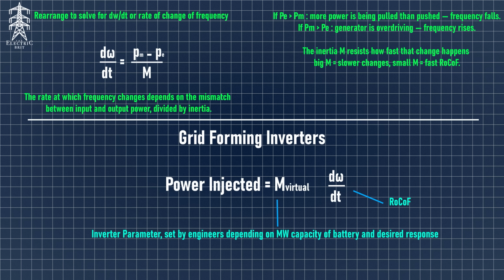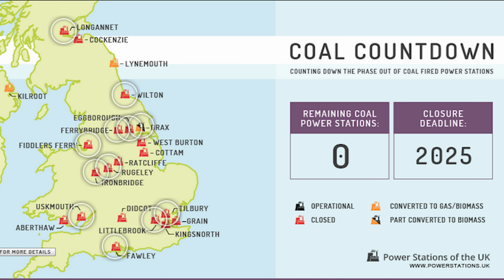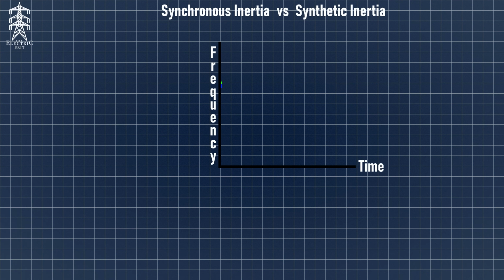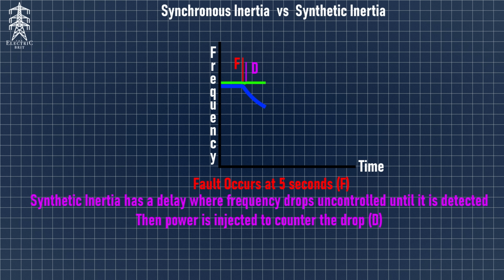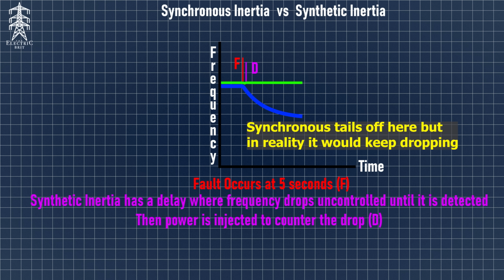Grid forming is becoming essential because historically the stability of the grid came from the spinning mass or inertia of big coal and gas turbines. As these older synchronous machines retire, we need renewables to help stabilise frequency changes by rapidly responding. New grid forming wind, battery and some solar systems can simulate this inertia electronically, known as synthetic inertia, helping to keep the grid steady during disturbances.